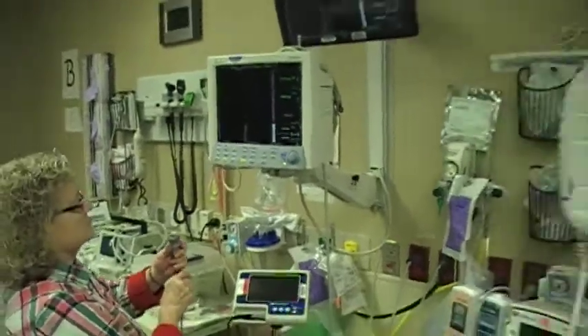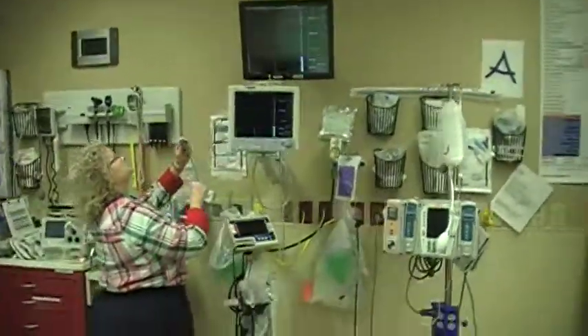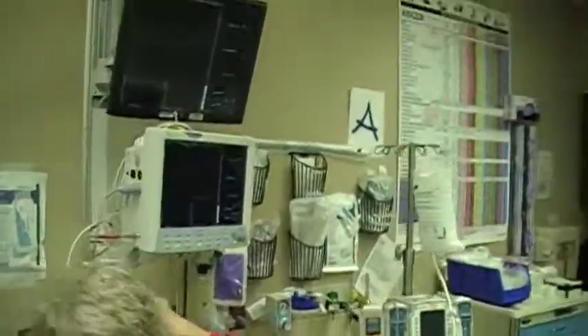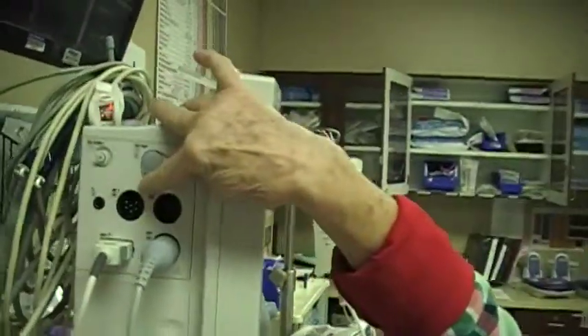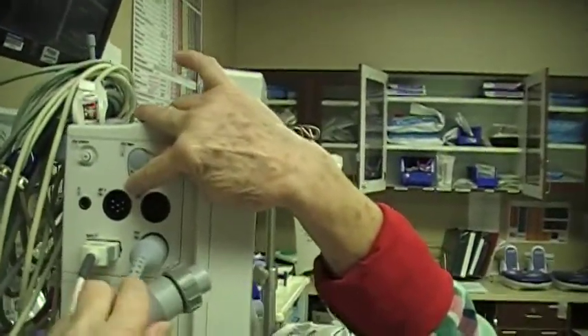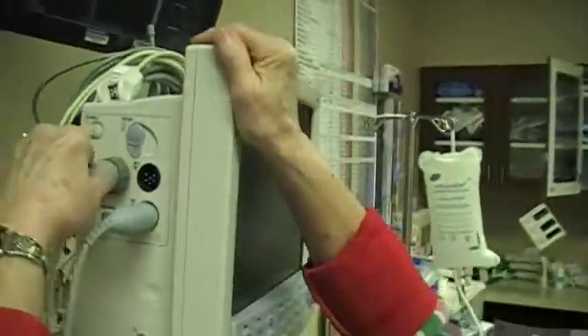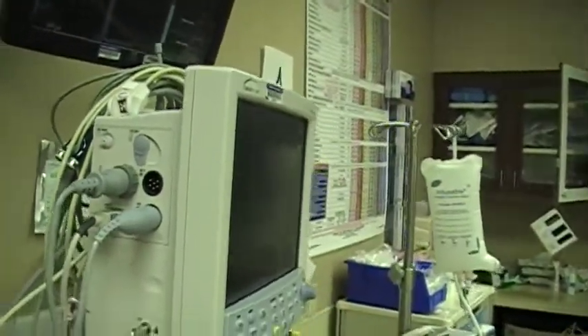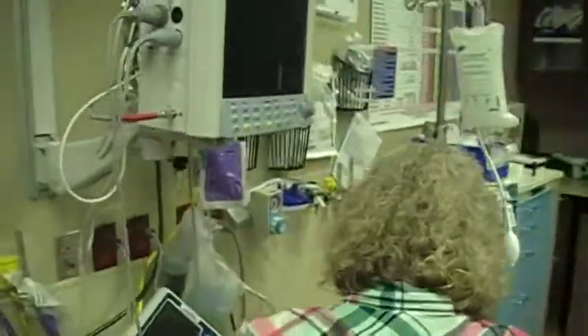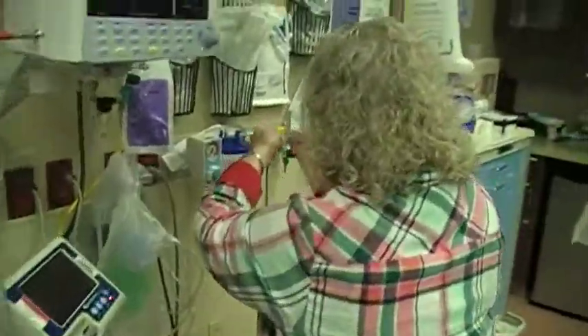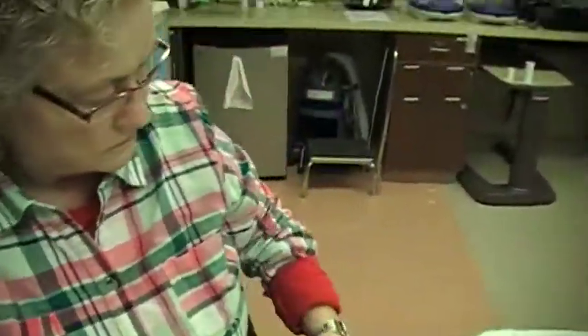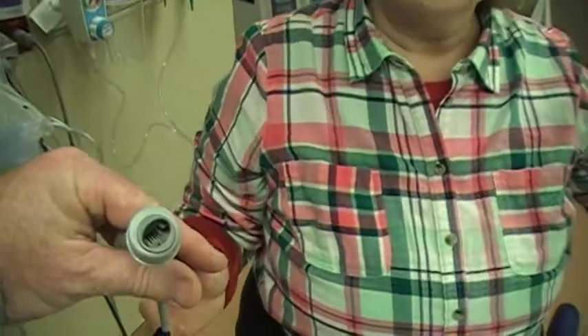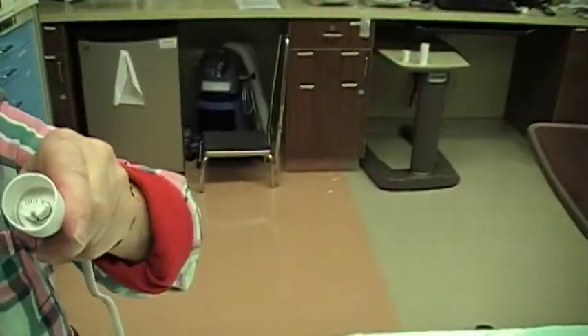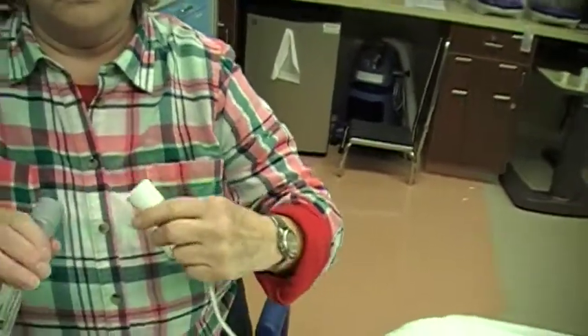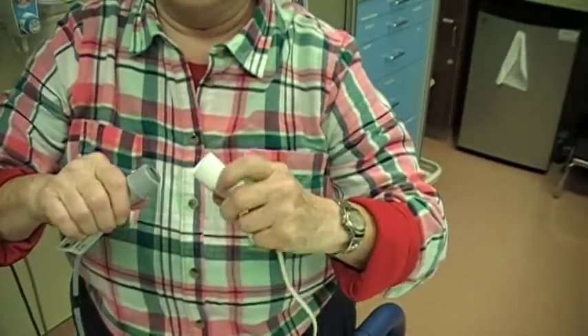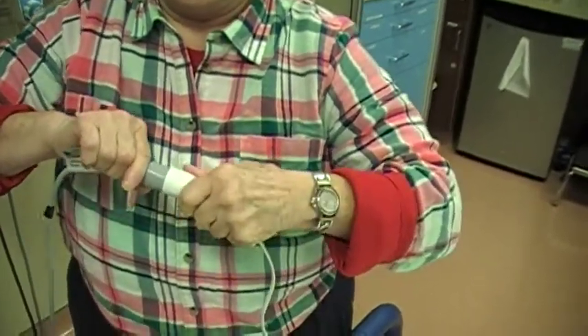And I'm going to walk around so that we can visualize where you hook up the transducer tubing. The transducer tubing is inserted into IBP 1. You can put it in IBP 1 or 2, it really doesn't matter. But there's a little flange, so it only goes in one way. Now that that is hooked up, she is going to take the other end of the transducer cable, and she's going to hook it to the component for the tubing itself. Only goes in one way. If you try and it doesn't go, rotate it until it fits.